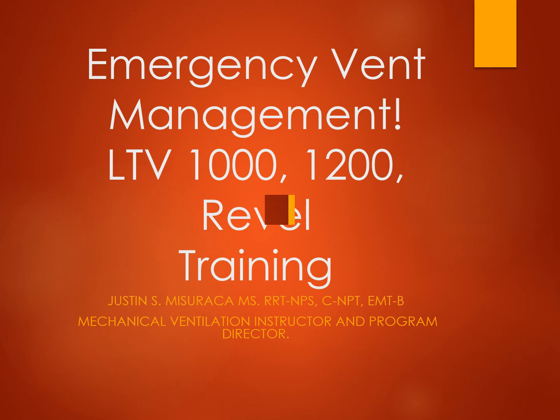So the LTV and the 1200 and Revel, they're not altitude compensated. There are ventilators out there that will say that they're altitude compensated if it's dialed in. So if that's the case, then you would have to dial that in to the ventilator and pay very close attention to that. Remember, when you're coming back down in elevation, you'd have to adjust it again. There's other ventilators out there like the Hamilton, the Eagle, Eagle Impact, a couple other transport ventilators that will have altitude compensation. That's great. Then you don't have to worry about it.